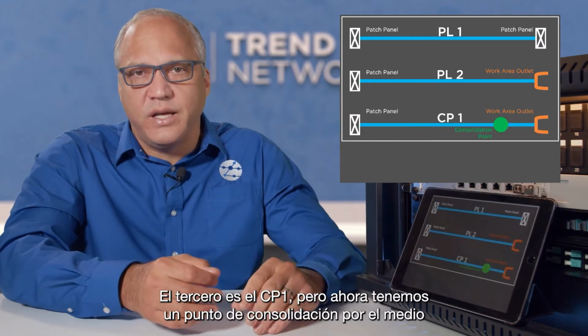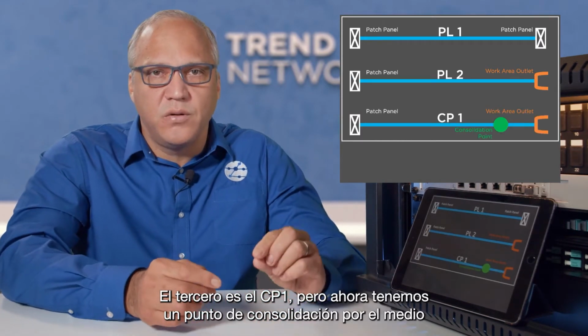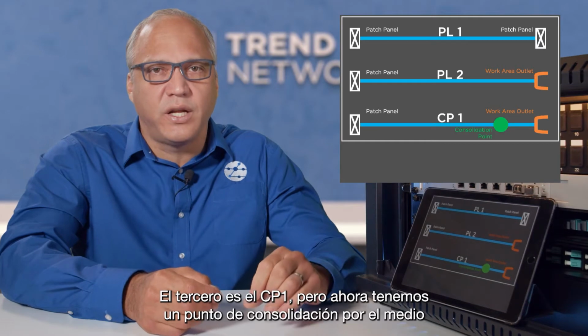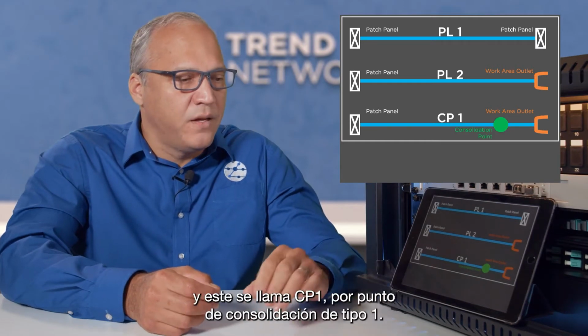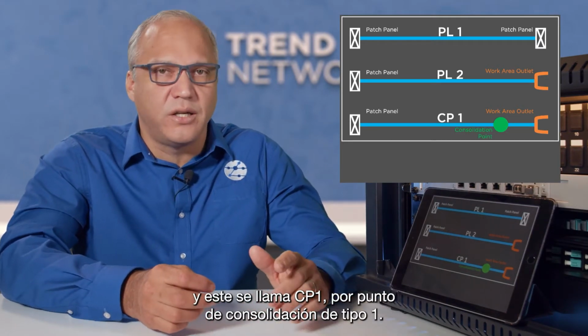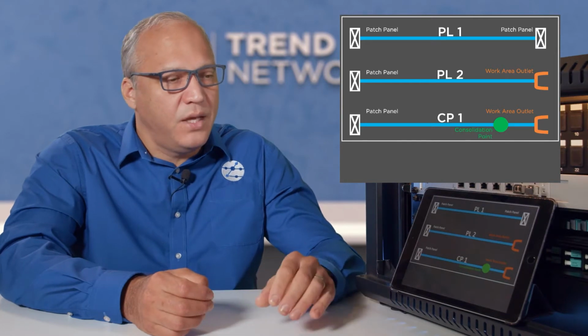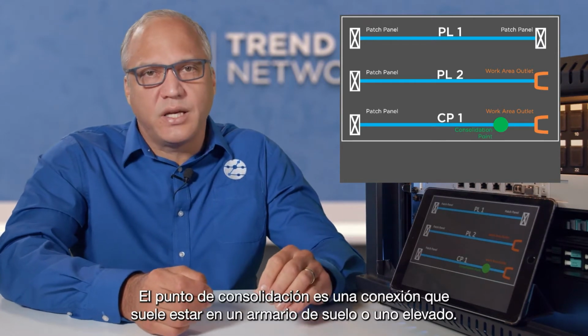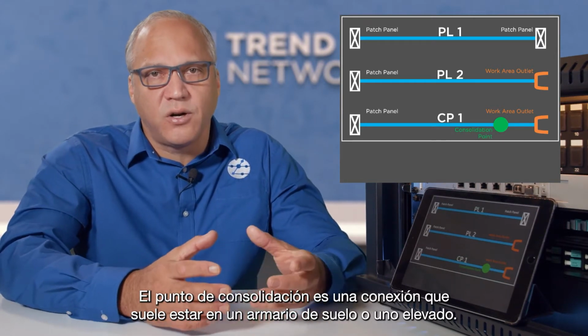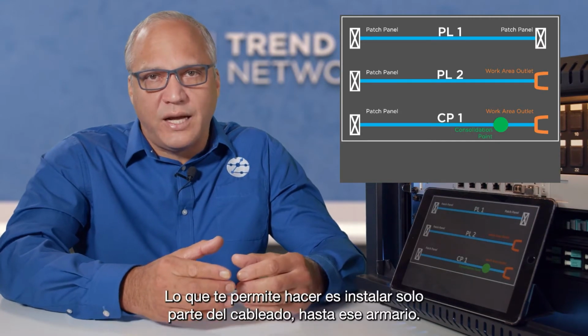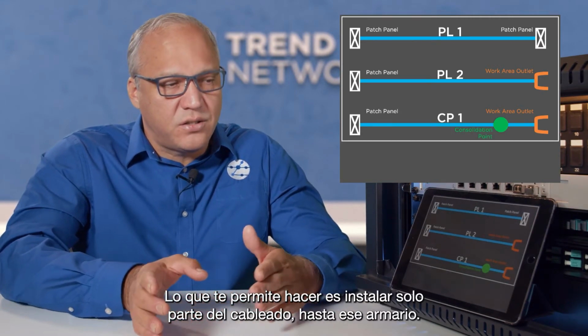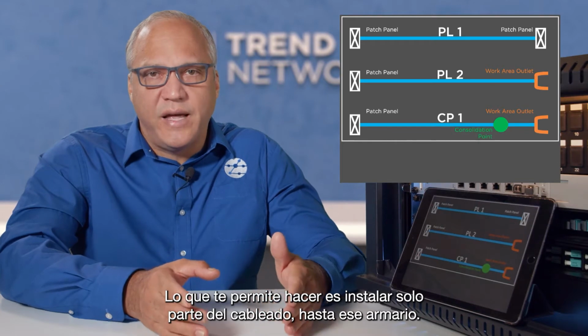The third is CP1, but now you have a consolidation point connection in the middle somewhere. And that's called a CP1 for consolidation point type 1. And the consolidation point is a connection. It's usually in a floor box or an overhead box. And what it allows you to do is install part of the cabling up to that box.